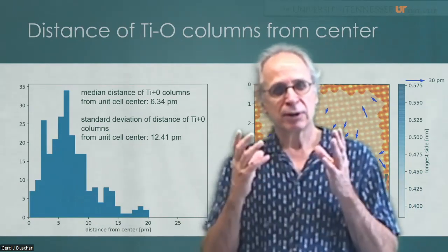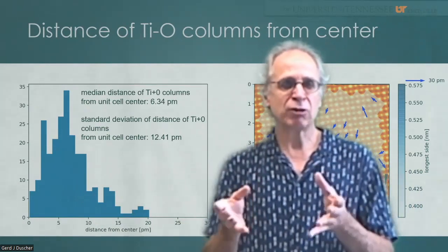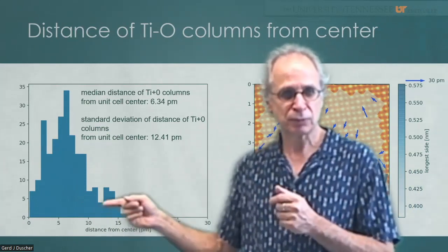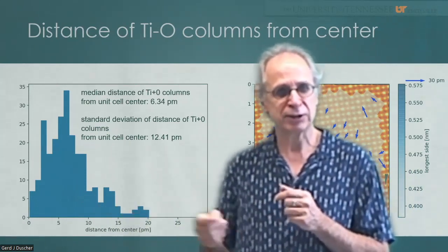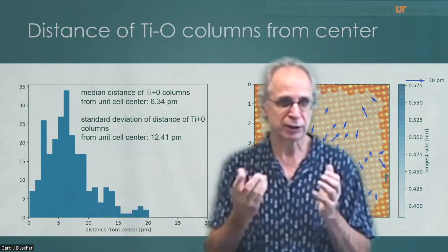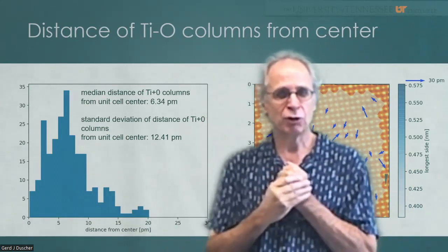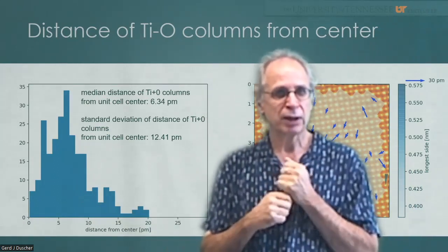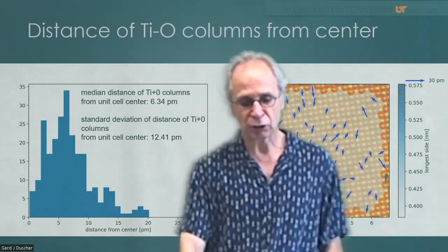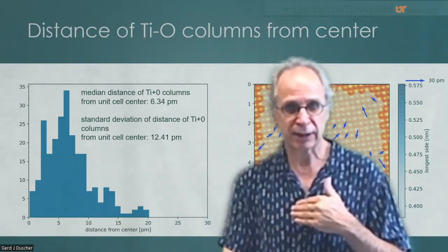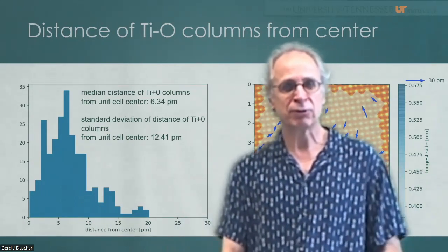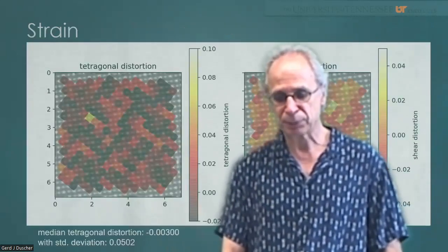And you can only reach this kind of precision in the single-digit picometer if you oversample your images, and if you know your drift and cancel that part out, and if you have a very stable microscope.